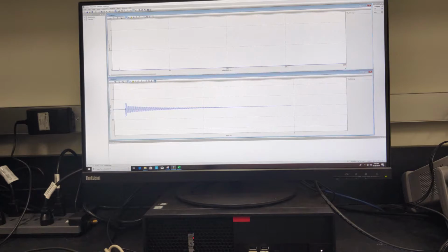Now this is the second strike. We can auto scale to make the curve clearer, but as you can see, this strike is not good because in the first several cycles the magnitude is too big, which means the hammer bounced back on the beam. Usually I will start a new capturing. Just stop the capturing and click the single shot again, which will start our new capturing.